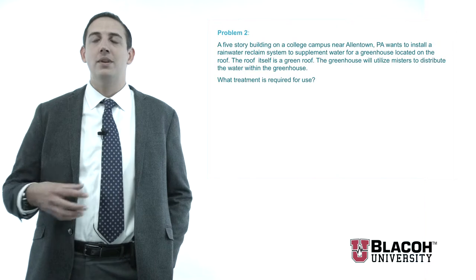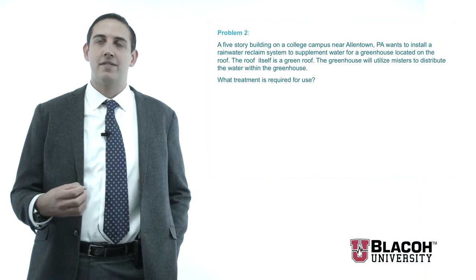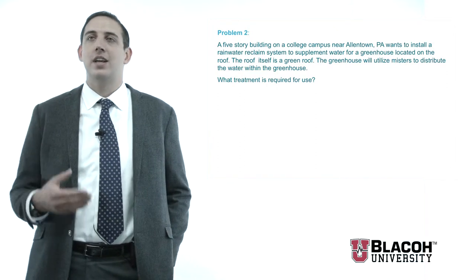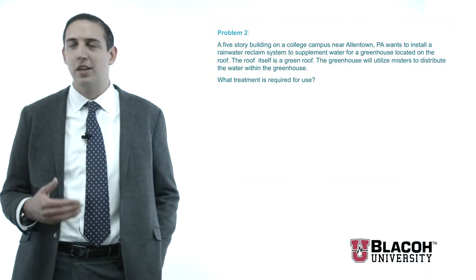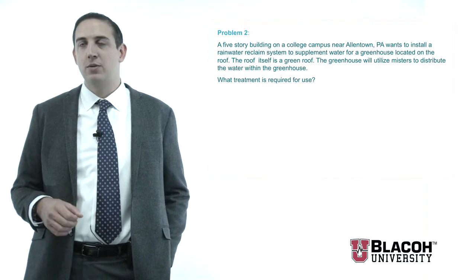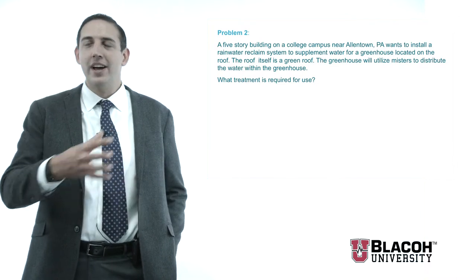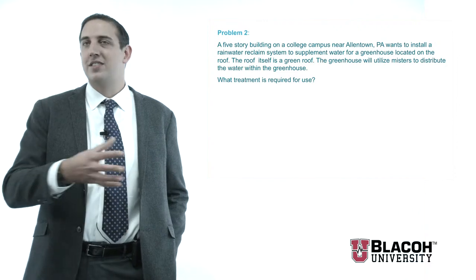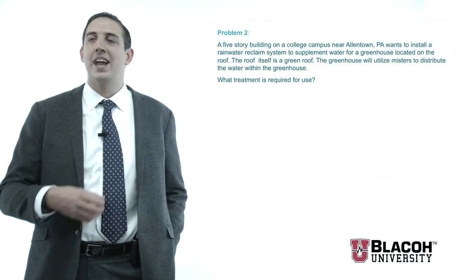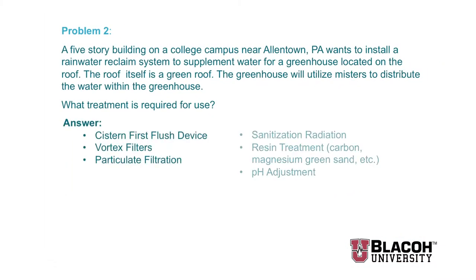You are also going through a mister. For those unfamiliar with misting or fog machines, they use very finely filtered water and a corona or spark to shoot it out as a mist. This means we need to get the water down to a very low particulate level or we risk clogging the system. We have the green roof situation to deal with, we're five stories above the ground so we won't see a lot of leaves, but we do need to temper our water and heavily filter it to avoid clogging the devices within the greenhouse.